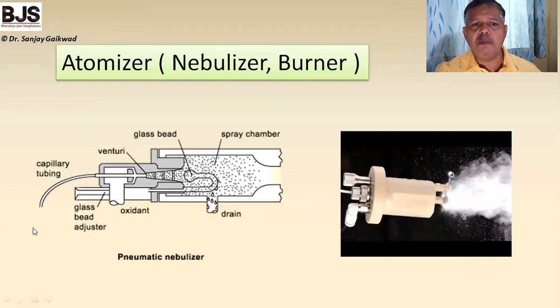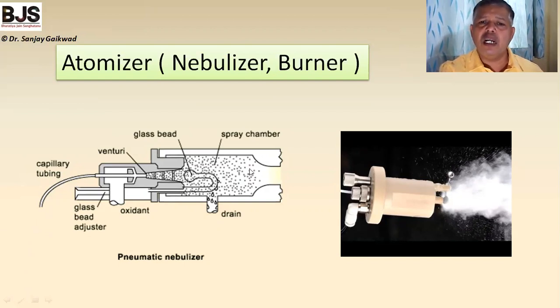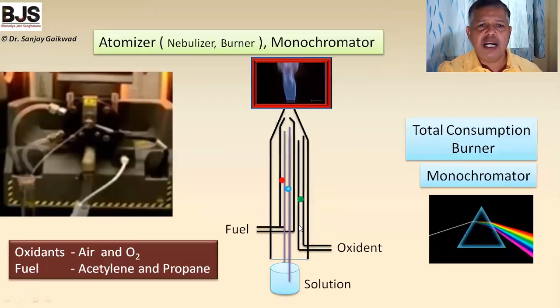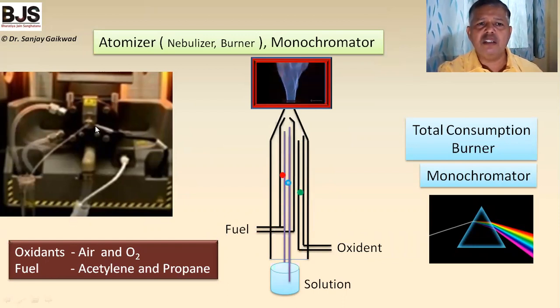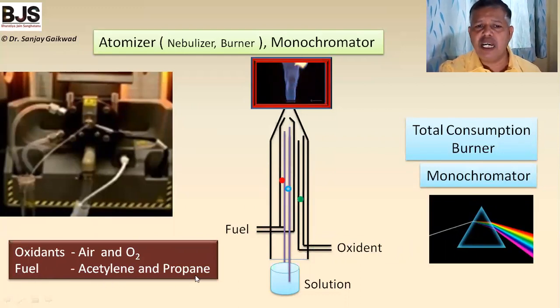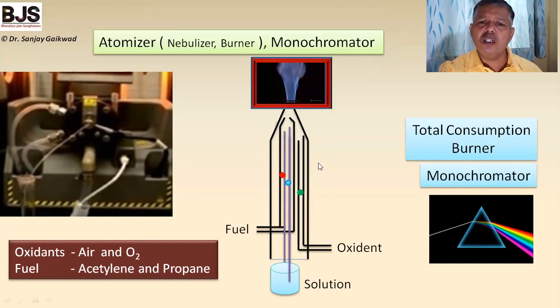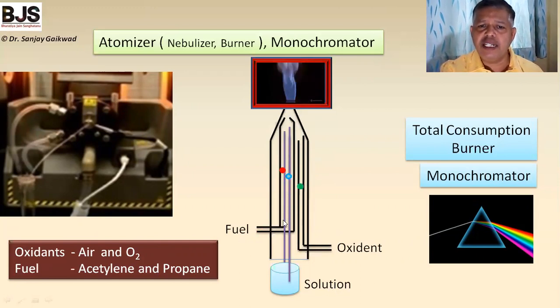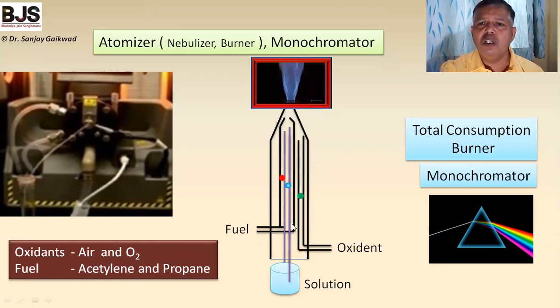The function of the atomizer is to convert the aspirated solution into a very fine fog — very small droplets — which enters directly into the flame. The oxidant may be air or oxygen, and the fuel may be acetylene, LPG such as propane, or nitrous oxide when hard metals need to be detected. The total consumption burner passes fuel and oxidant directly to the burner. Waste gases from the flame are removed using an exhaust chimney or exhaust fan.